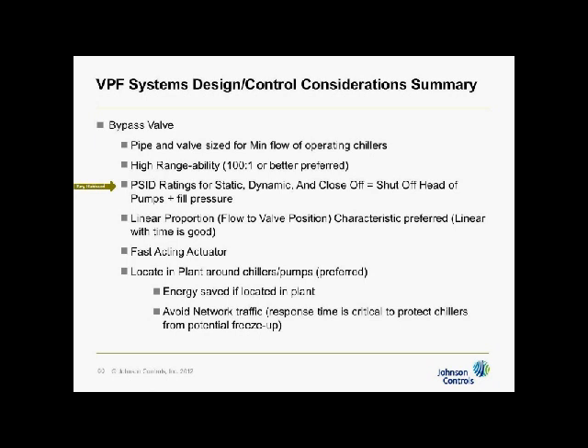If you don't have enough pressure differential rating on that valve, you could burst it. The dynamic rating is the ability for the seat to remain in place and not blow out because the pressure differential is too great. And the close-off rating is the torque of the motor, the actuator on the valve. Does it have enough torque to close down under the pressure differential you could see at shutoff head? It's possible to see it in the system. And if it can't close, it'll sit there and chatter. Okay? So PSID ratings need to be up near shutoff head of the pump for static, dynamic, and close-off.